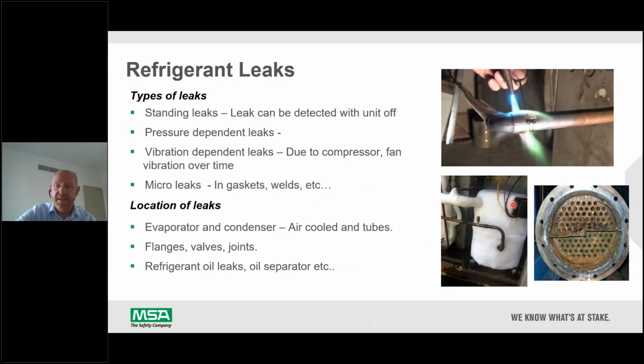So leaks: where do the leaks come from, and what are the different types of refrigerant leaks we have? There are standing leaks, which are leaks that can be detected when the unit is off. All refrigeration systems turn off at some point, either on defrost or when they've met temperature. So standing leaks are best detected when the unit's off. Then we have pressure dependent leaks, where the compressor needs to be running in order to push the gas out of the system. These are still the major leaks, where you have a large volume of gas coming out of the system. And then over time, we have leaks which happen in piping or in gaskets or welds due to vibration of the compressor and fans. And then micro leaks occur sometimes due to corrosion in gaskets and welds, etc. So these are all sources of leaks that can happen in a system.